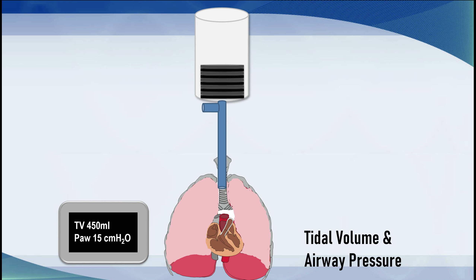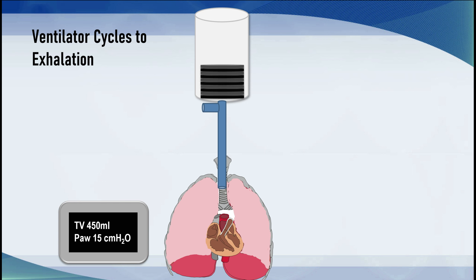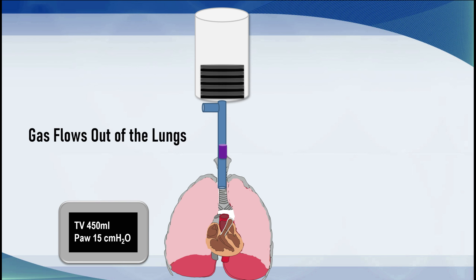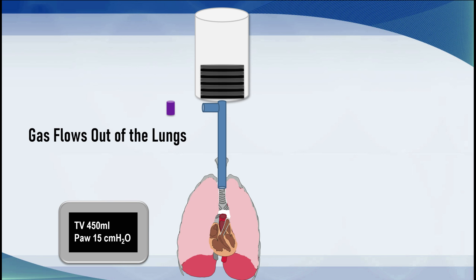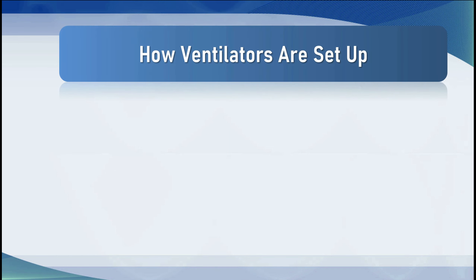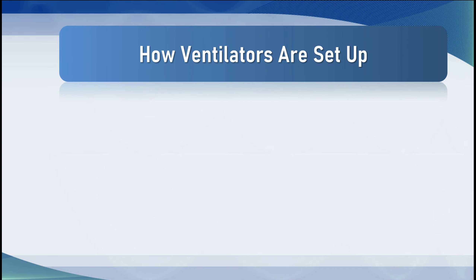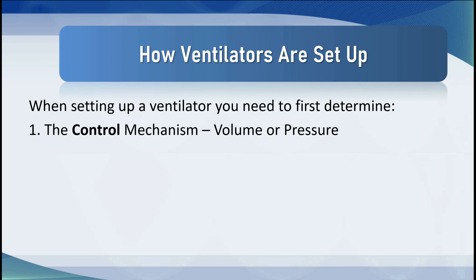Depending on how you set up the ventilator, it will cycle to exhalation and the gas that has been sent into the lungs is released and vented off through an exhalation valve. When setting up a ventilator, we first need to determine the control mechanism — volume or pressure.